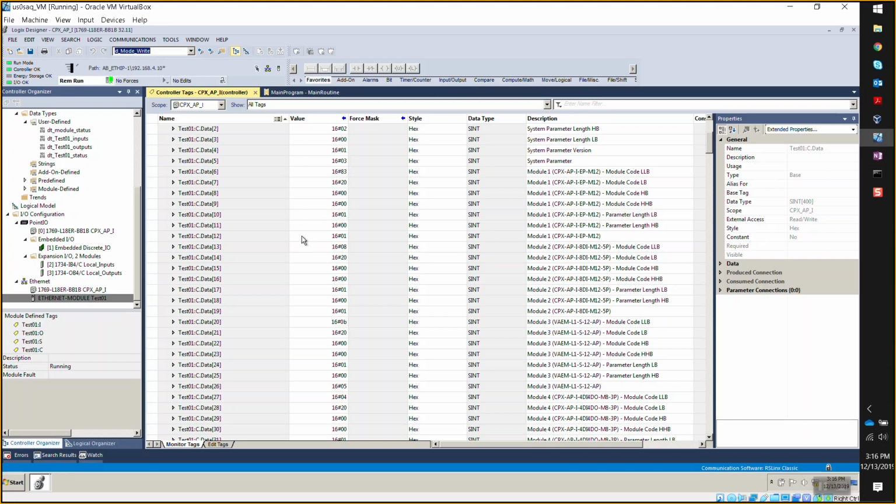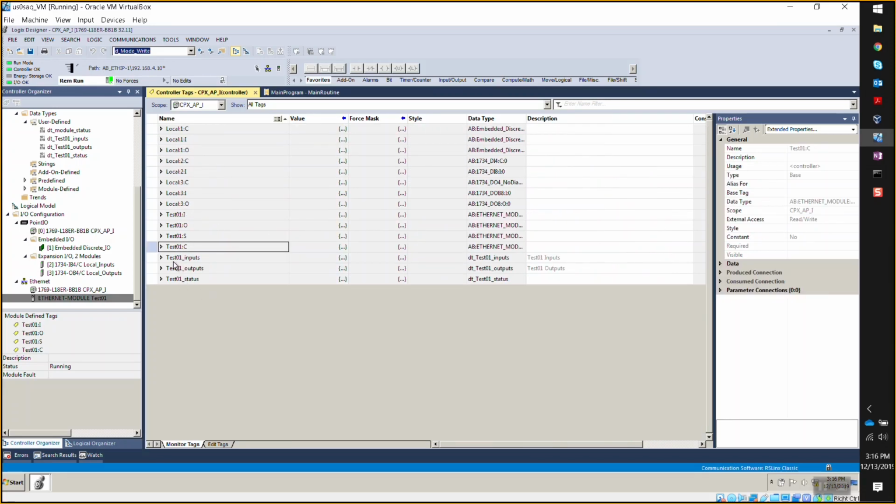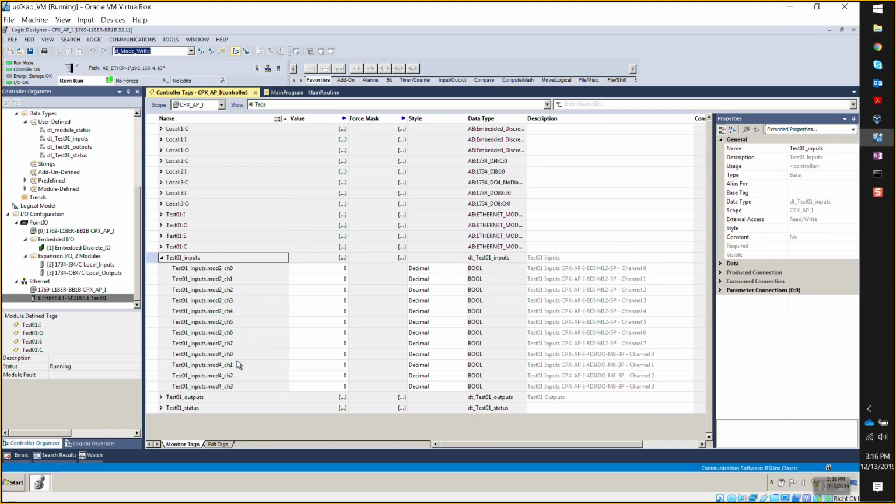I think the three different paths that you showed me are great. I mean, there are differences between each other, of course. I think it would be up to every programmer to follow the one that they like the most. Personally, I think in most cases I will go with the L5X, just because of what I explained earlier. You get the UDTs, you get everything already imported in here. It takes me maybe one or two more minutes to export and import, but it's just three rungs, so it's not a big deal. And the benefits that I get are huge compared to the other ones. I would recommend that way all the time.